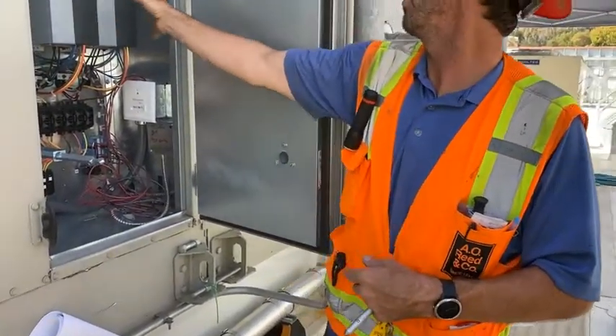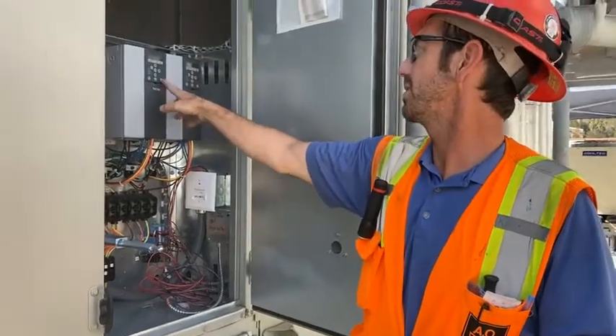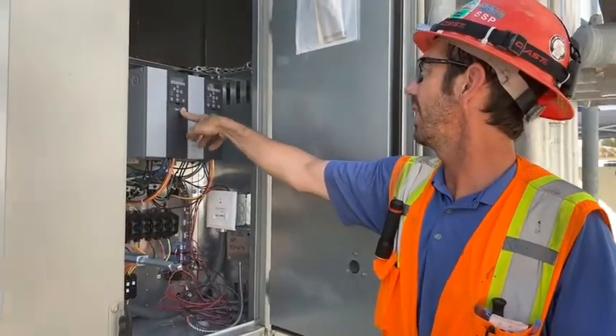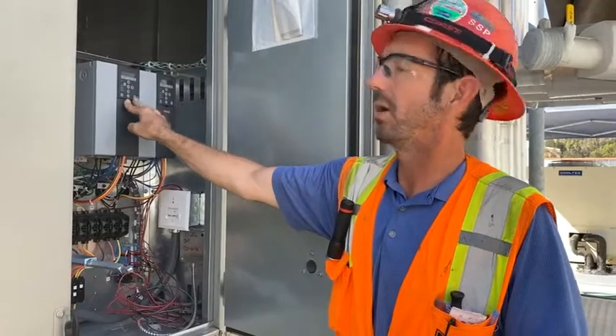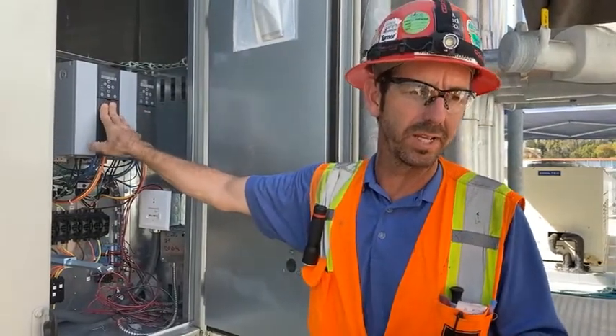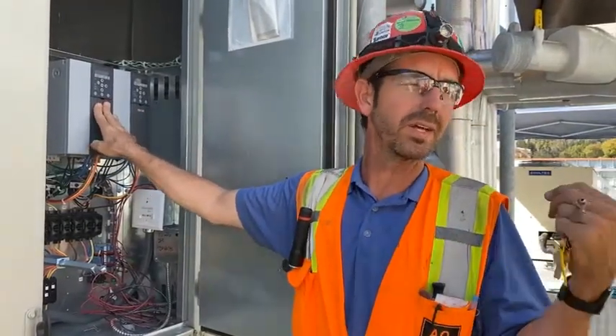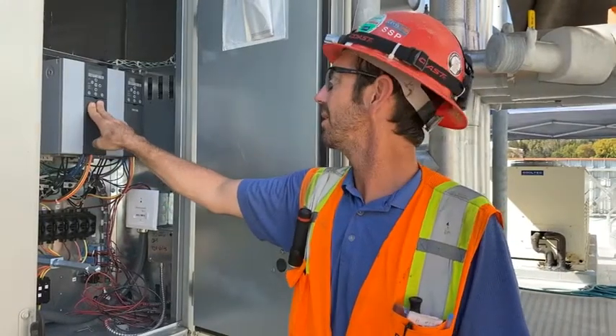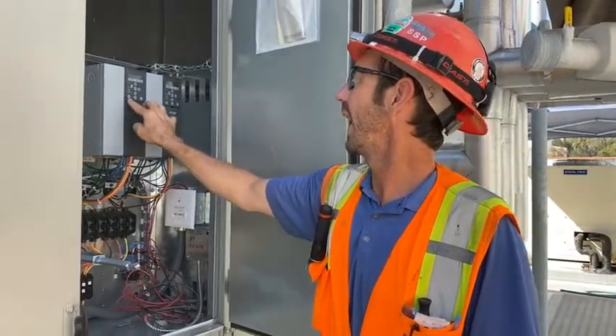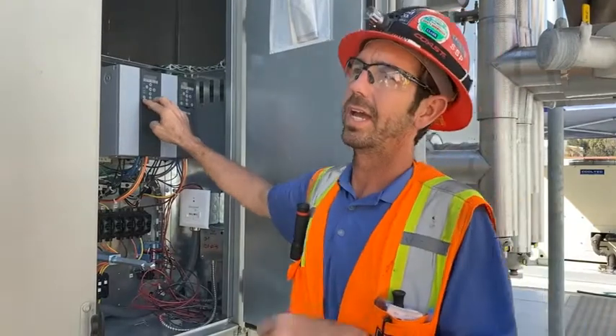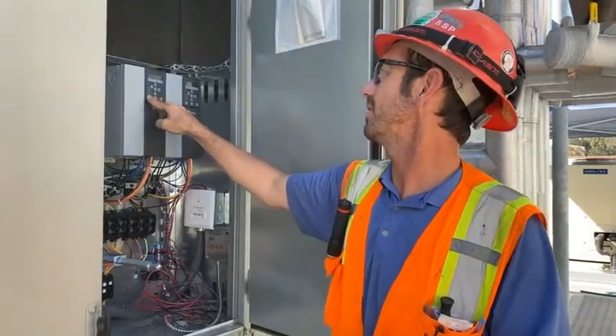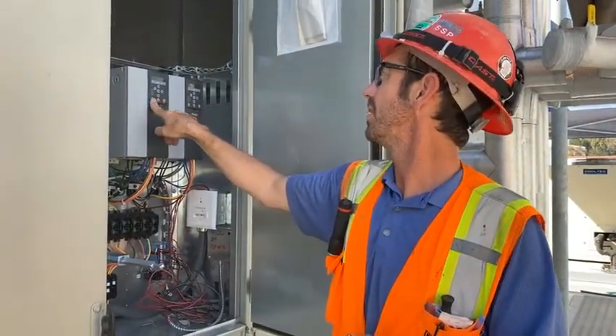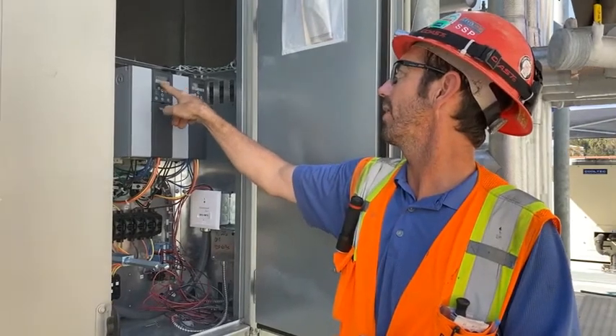Again, the most important part with these drives when you're doing your inspections is that we're in auto, okay? That will allow the BMS guys to turn on the unit and then ramp it accordingly depending on the static pressure in the ductwork, okay? Hand obviously will turn on the unit. In hand mode, at first it'll turn to the minimum speed. So when I press hand, we get a black bar across here.